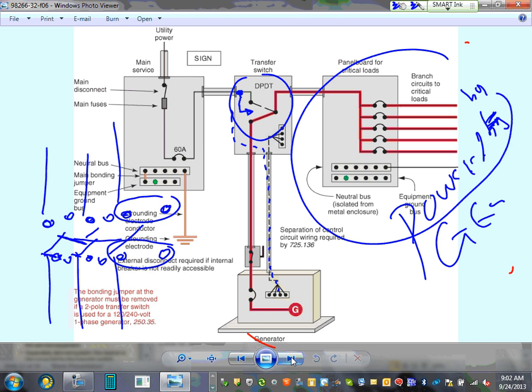Any comments, any questions? Typically, what we do, guys, is you drive a ground rod and ground your generator, the frame of your generator. Or if you're outside, and the utility ground rod is right in the area, you just tie it to the ground rod because the utility ground rod is right in the backyard. So you just take a number 10 copper, tie it to the utility transformer, and you're good to go.